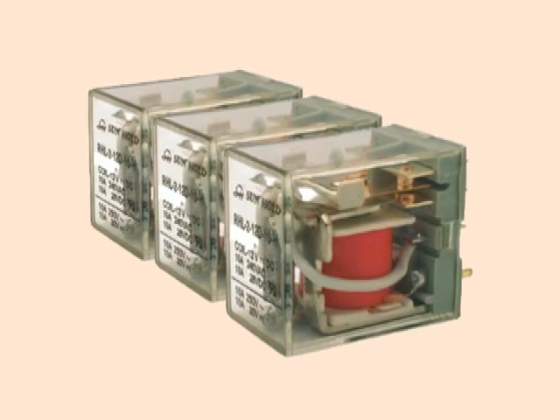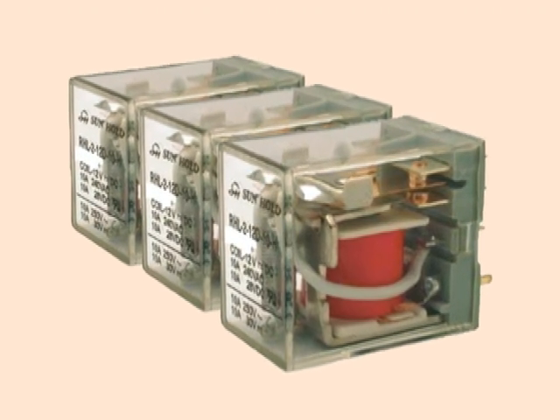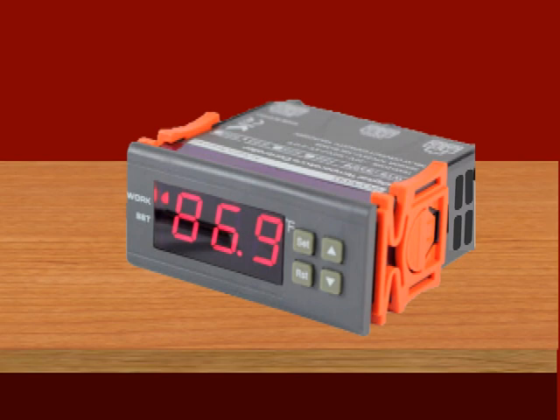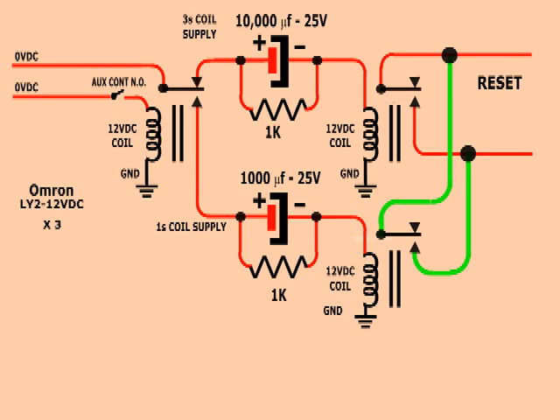The relays we used are identical, coil type operated with 12 volts direct current. Adjusting the auxiliary thermostat to match the temperatures of the original thermostat would provide us with two sequential signal lines which would operate the other pair of relays, one at a time, one relay to deliver a one second continuity pulse to the reset button, and one relay to deliver a three second continuity pulse to the reset button.